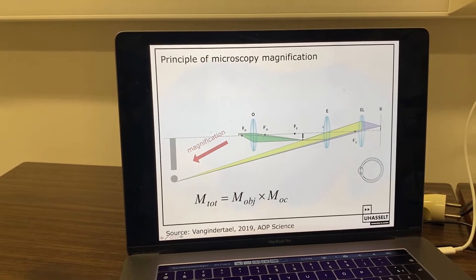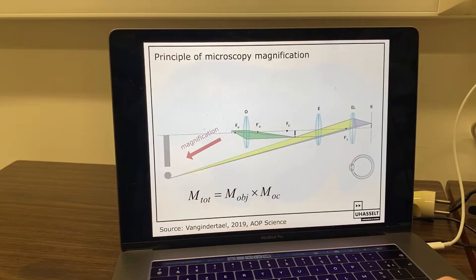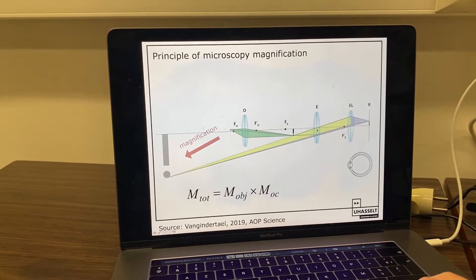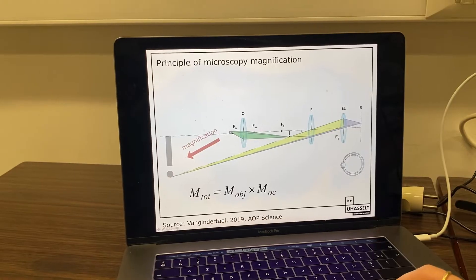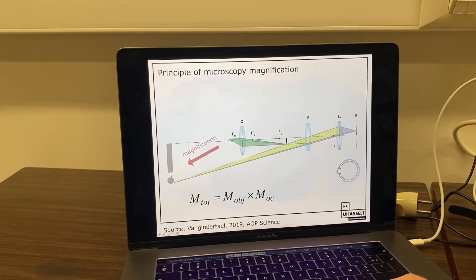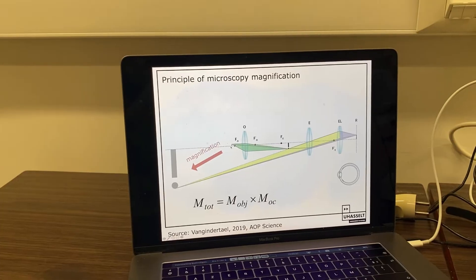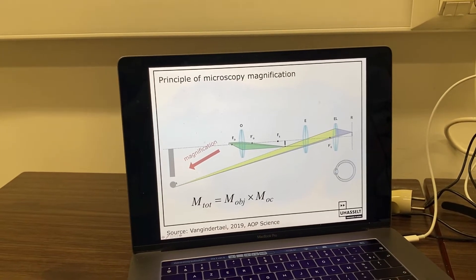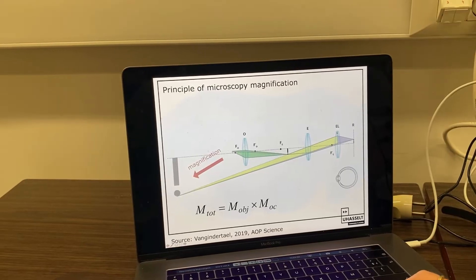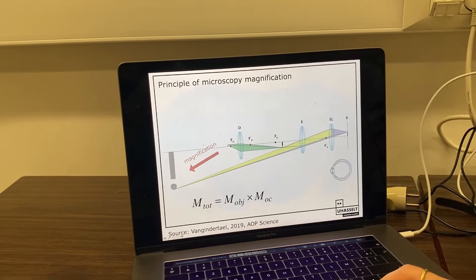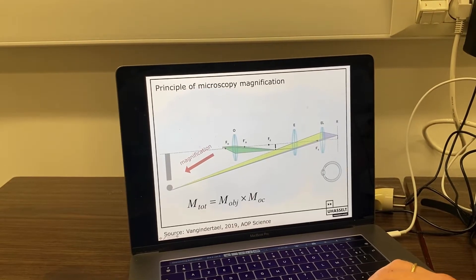In the microscope there's a second lens, the eyepiece lens, which is the one we look through with our eyes. This eyepiece lens doesn't image the image formed by the objective lens into real space. It images it in virtual space. So the total magnification of the microscope is the product of the magnification by the objective lens and the magnification by the eyepiece lens in virtual space. Our eye lens finally images this virtual image onto our retina, giving us a final view of the sample.